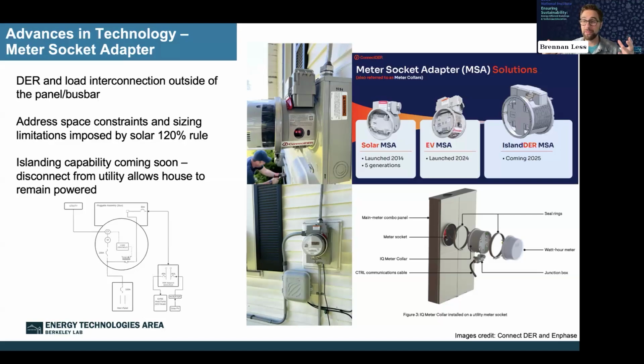The main idea is that rather than connecting a load or a power source into the panel, which might have space or capacity constraints, maybe we can do a connection that's actually right up at the meter. We totally stay out of the panel, making a connection by connecting to the service wires at the meter. This lets us get around some of the issues we have in homes with smaller panels. The NEC, for example, limits the amount of solar or battery power you could feed into a panel based on the rating of the bus bar and the main breaker of that panel. This lets you get around that.